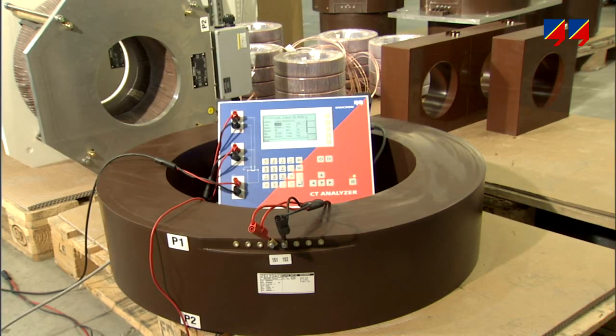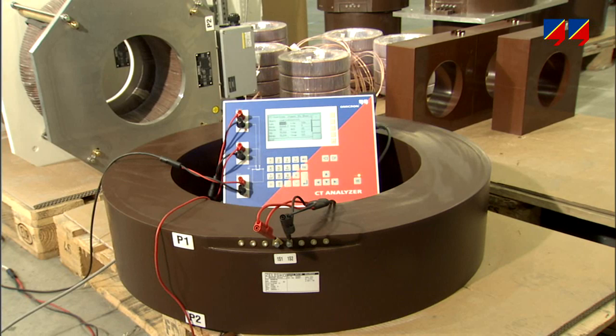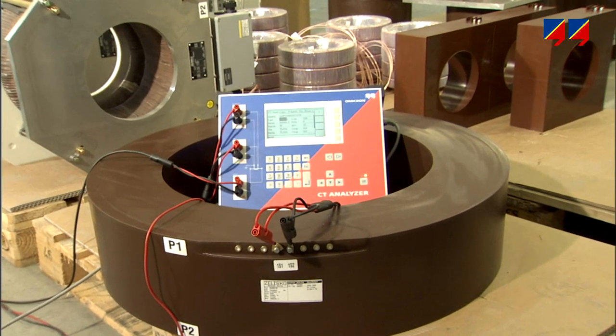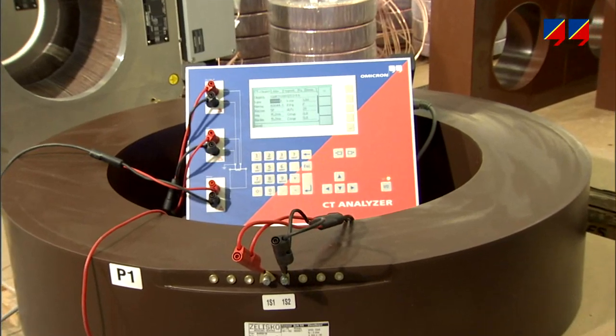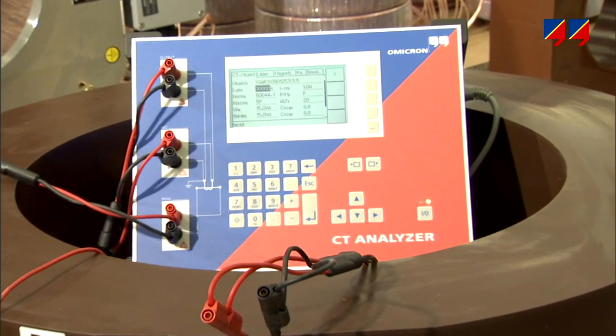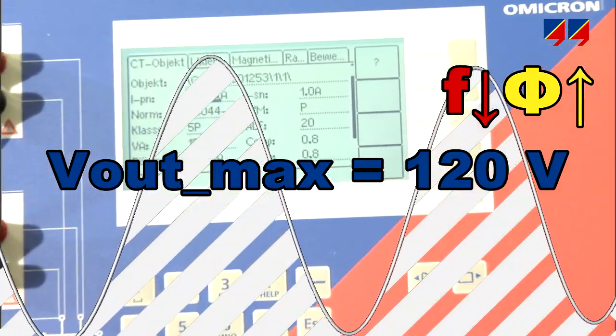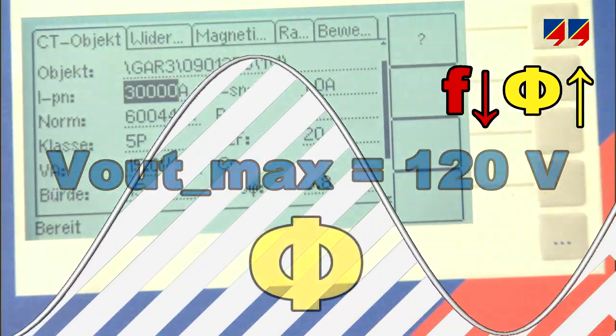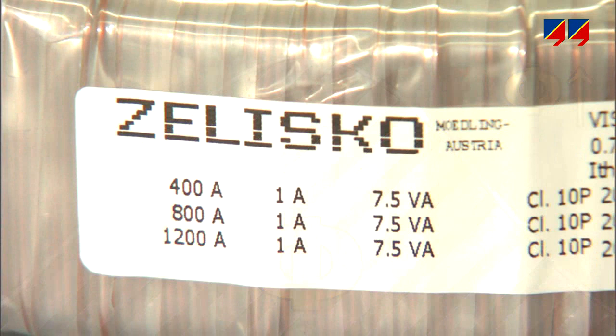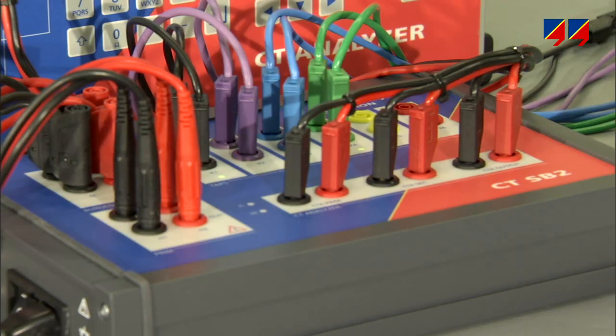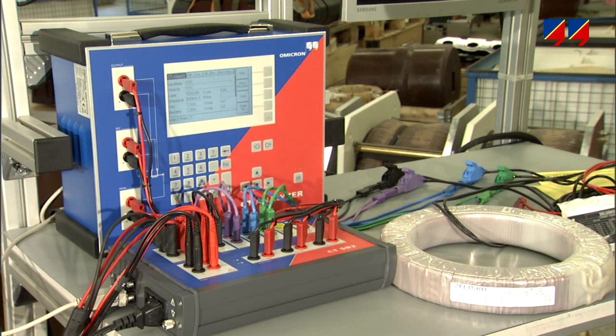CT analyzer provides an automatic pass or fail assessment. For special CTs, such as those with very high turns ratio or with a very high knee point voltage, CT analyzer's principle of testing from the secondary side avoids the need for heavy cables, and its low voltage, low frequency method makes excitation curve measurement very safe. For CTs with tapped secondary winding, the CT analyzer switchbox allows the simultaneous connection of the taps and the execution of the test in one automatic procedure.